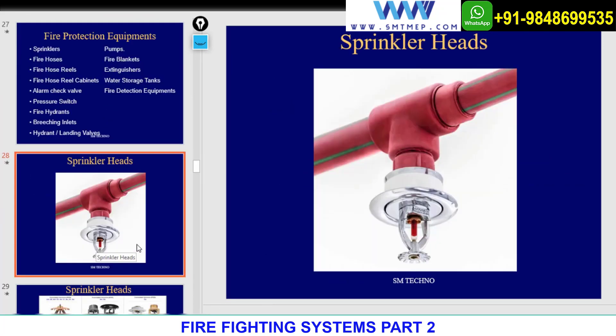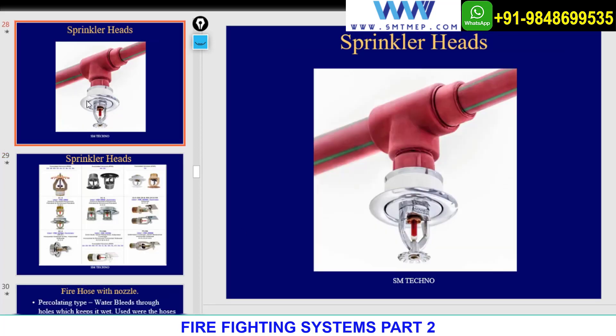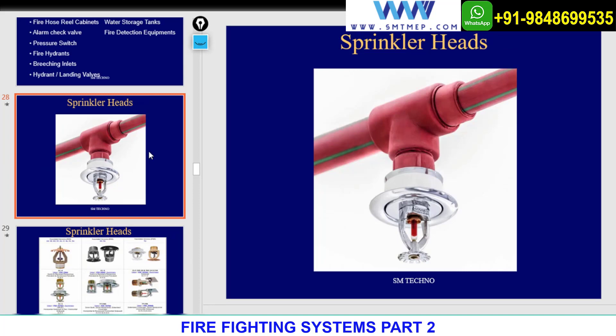For fire protection equipment, starting with sprinklers: in actual practice we have different types — bulb type and fusible link type — with different thermal ratings and different types as per different applications. The most common types shown are pendant and recessed pendant. A question was raised about whether a PVC pipe is shown in the image. Generally, we will not find PVC pipe in fire protection; you'll find black steel, GI, or mild steel.